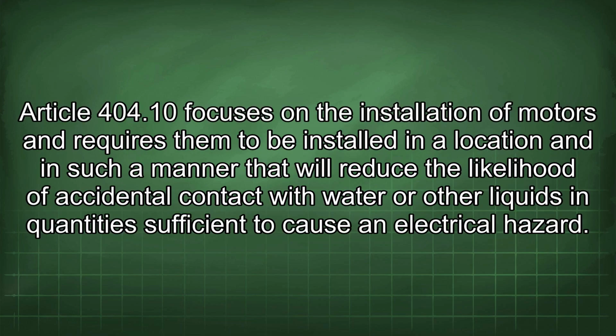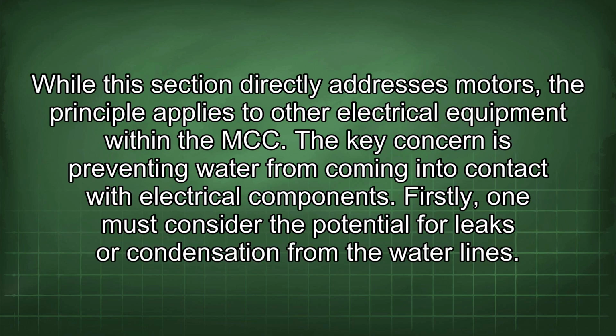Article 404.10 focuses on the installation of motors and requires them to be installed in a location and in such a manner that will reduce the likelihood of accidental contact with water or other liquids in quantities sufficient to cause an electrical hazard. While this section directly addresses motors, the principle applies to other electrical equipment within the MCC. The key concern is preventing water from coming into contact with electrical components.